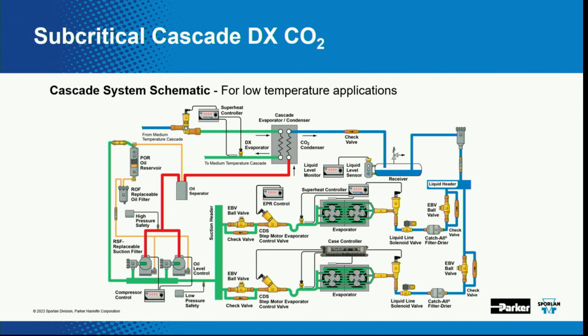Yeah, I was just going to help him out. So you're looking at that flat plate heat exchanger up there. That's running your standard medium temperature. That's not running like 80 degrees. So when you're dumping that CO2 coming out of the discharge on your CO2 compressors, that's not as hot as your normal discharge is. Your discharge has to be dropping around 400 pounds, and then for your low temp, you're going to drop it down to like 200 in that flat plate heat exchanger. So it's not as high pressure as what you're thinking, and you're not condensing it necessarily. I mean, you're condensing it, but...